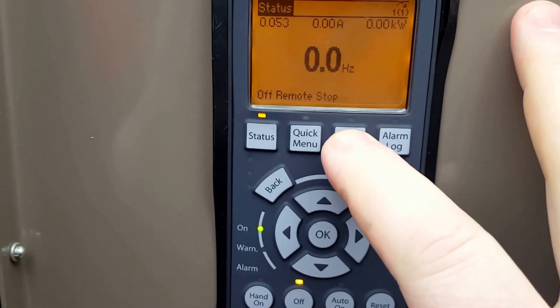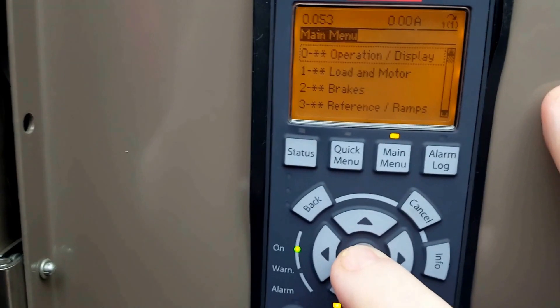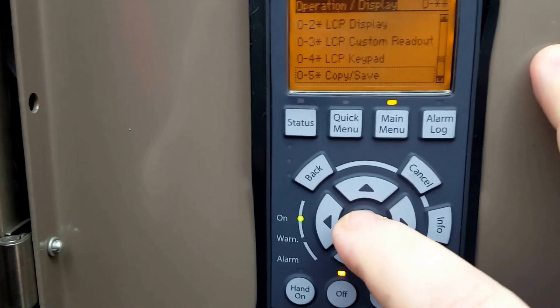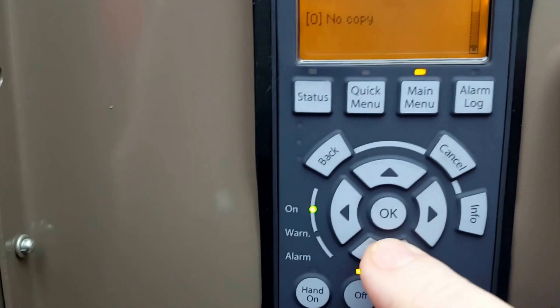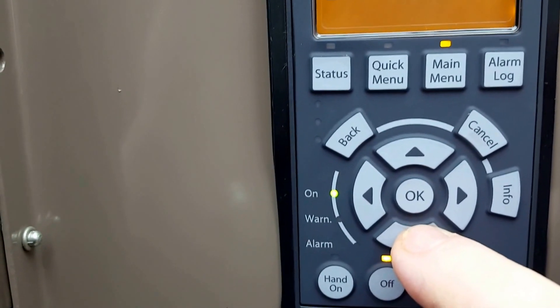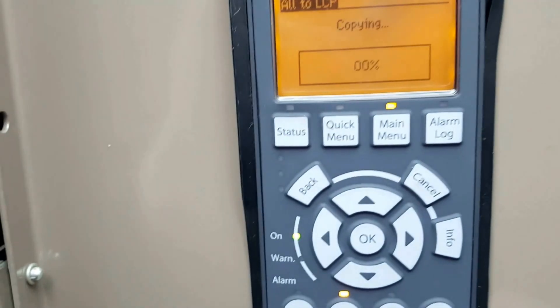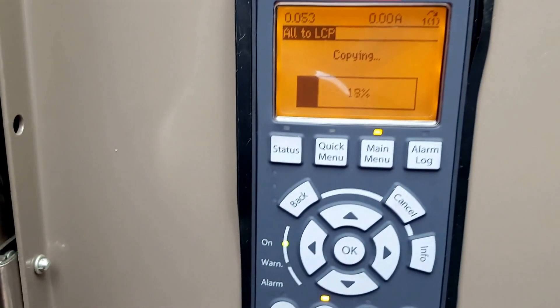The first step in the process is to put the drive in stop mode — it will not let you do anything unless you have it in stop mode. Press your main menu button and then scroll to the correct parameter, which is going to be 050. What we are going to do is change this to All to LCP. Once we press the OK button, you can make your selection by scrolling up and down, and once you press OK again it is actually going to upload all of the parameters within the drive.